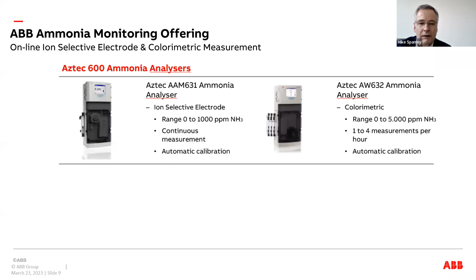If we look at the ion selective electrode, for most monitors we produce these days we have to consider what the customer wants. They're looking for lower maintenance, auto calibration, reagents that last longer, and servicing intervals to be as long as possible. It's about cost of ownership.